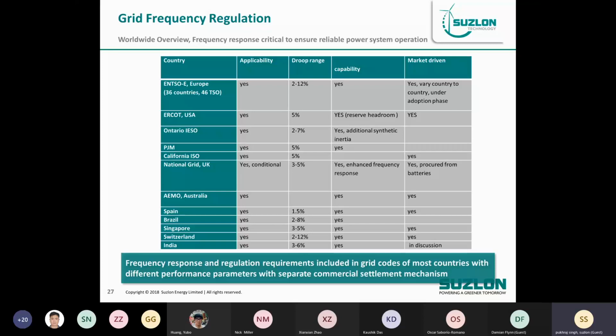In solar, because they don't have such a rotating mass, I have seen in some cases large capacitor banks, some small storage or some virtual inertia being created in order to fulfill these requirements in solar plants. But at least in a hybrid plant, where you have wind, solar and also storage, you can make a good choice of combination, either based on a pre-decided rule of which source to use under what conditions. That is quite helpful when you have these three components together to meet such stringent requirements of frequency regulation or synthetic inertia.